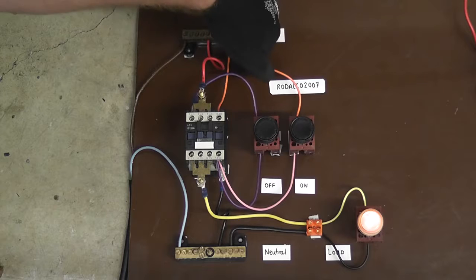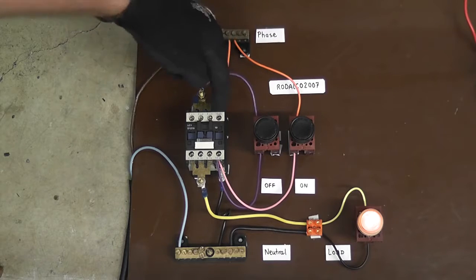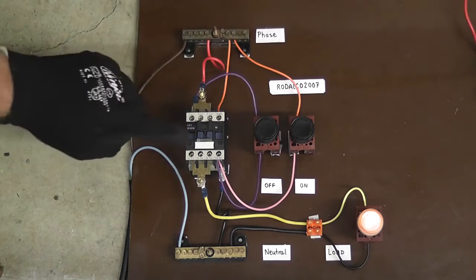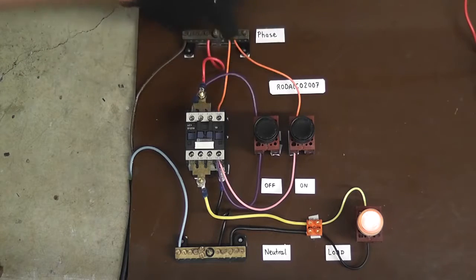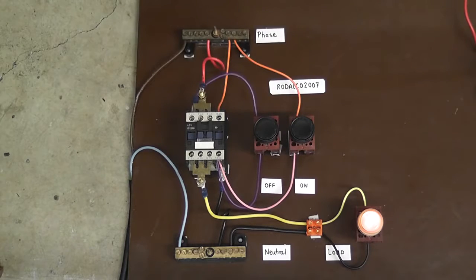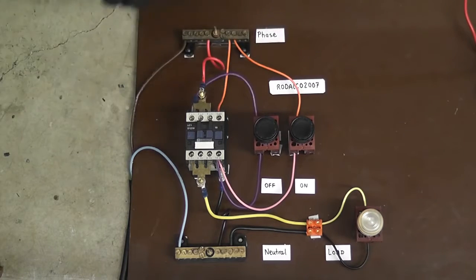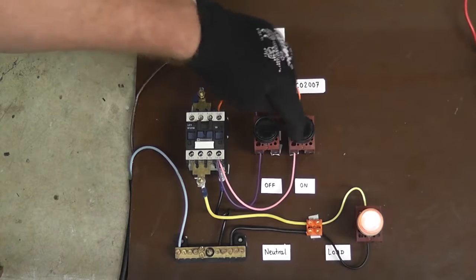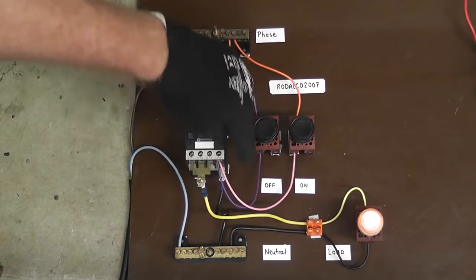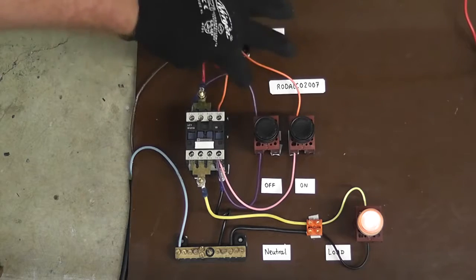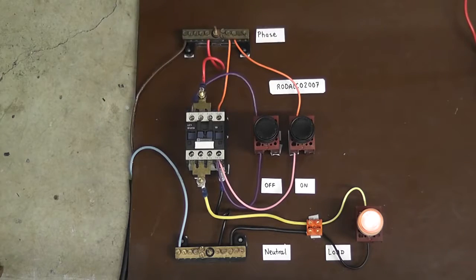The control wire goes on terminal 4, that's a spare normally open terminal, goes through the on button and the on button gets a supply from the phase so it's a latching contact so it's energized and it will latch itself. Push this, it energizes, goes through the jumper. This is the off button, goes through the jumper and drives the coil.